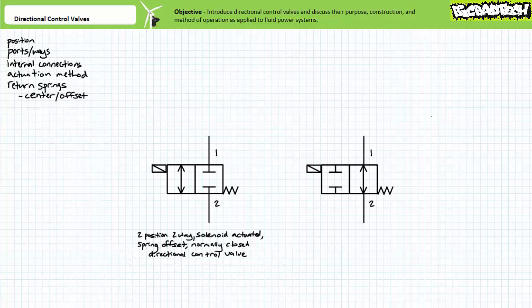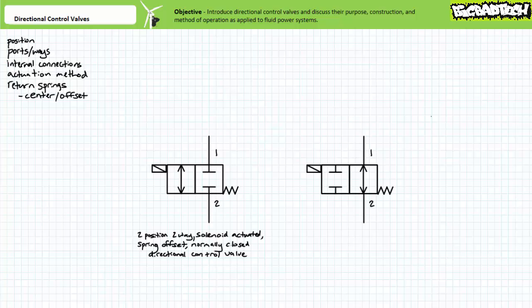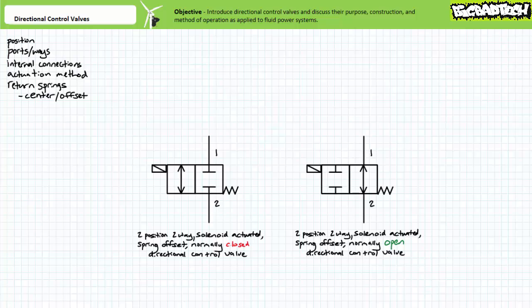Consider a subtle modification of this valve. Pause the lecture and see if you can determine the number of positions, the number of ways, the actuation method, and the deactivated state of this directional control valve. This directional control valve is almost identical to our first example — it is also a two-position, two-way, solenoid-actuated directional control valve. However, it is spring offset into a normally open position. In the absence of an electrical pilot signal, fluid can flow. In the presence of an electrical pilot signal, fluid flow is blocked.